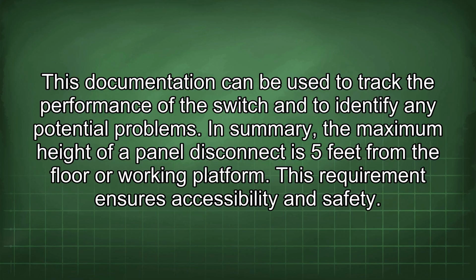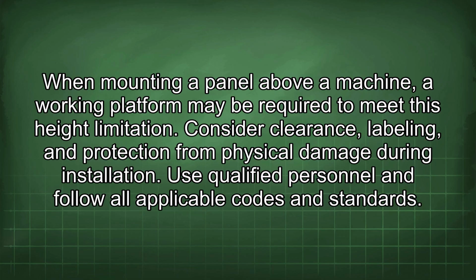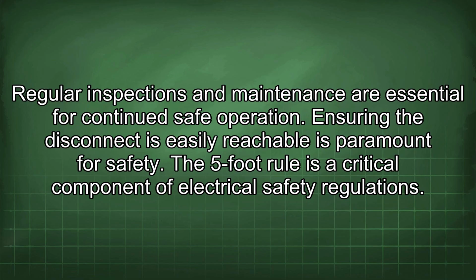In summary, the maximum height of a panel disconnect is 5 feet from the floor or working platform. This requirement ensures accessibility and safety. When mounting a panel above a machine, a working platform may be required to meet this height limitation. Consider clearance, labeling, and protection from physical damage during installation. Use qualified personnel and follow all applicable codes and standards. Regular inspections and maintenance are essential for continued safe operation. Ensuring the disconnect is easily reachable is paramount for safety. The 5-foot rule is a critical component of electrical safety regulations.